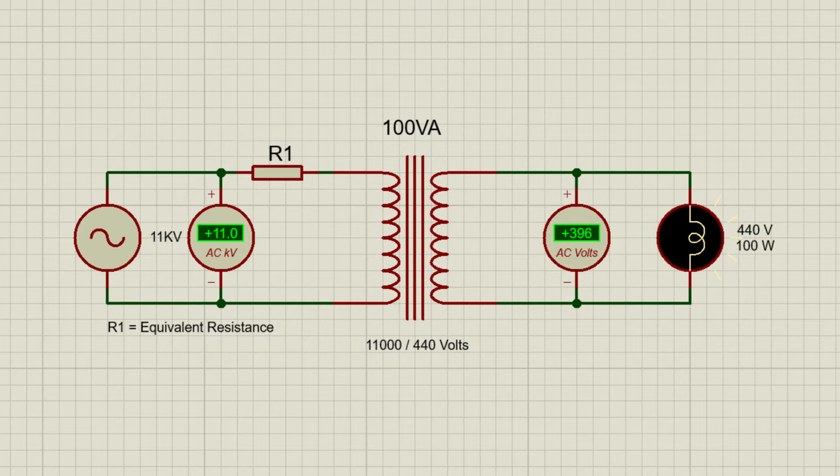So what is the percentage impedance of a transformer? It's a measure of the voltage drop that occurs when the transformer is fully loaded up to its rated secondary current. This voltage drop is due to the resistance and reactance of the transformer's winding.